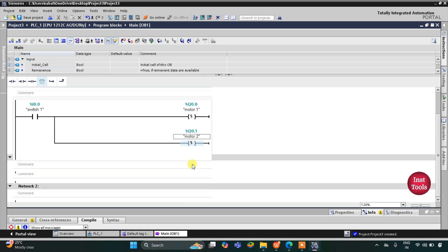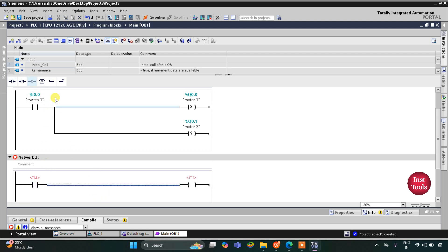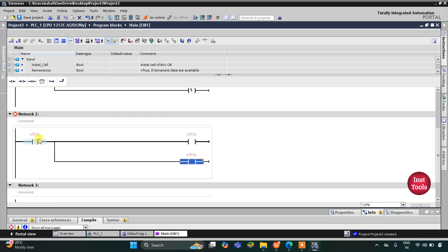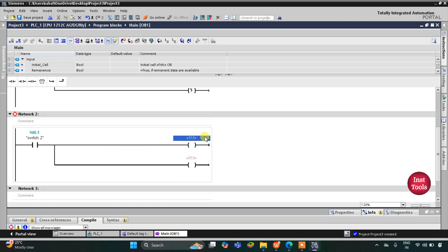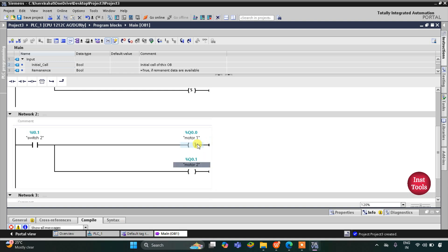To turn off motor 1 and motor 2 we will use reset coils and we will use switch 2. For that I will use network 2 and insert a normally open contact, then a coil, open the branch, and add one more coil. Switch 2 will be the contact to turn off motor 1 and motor 2.